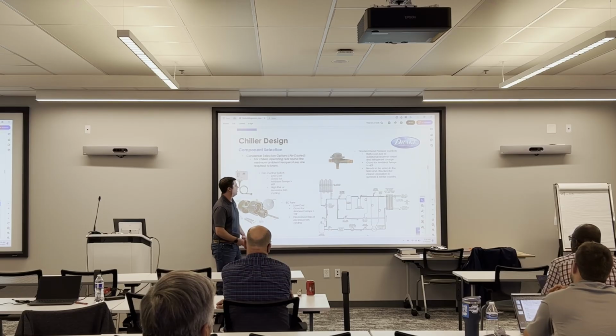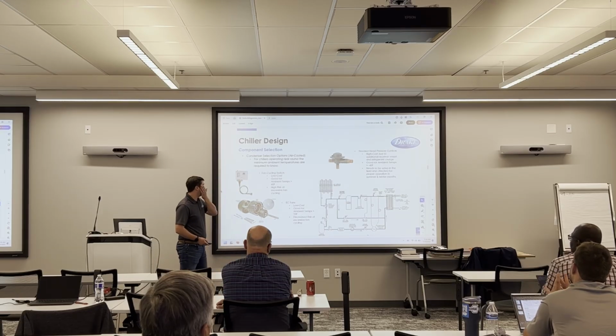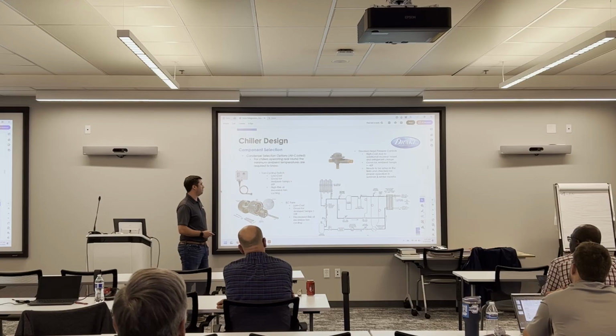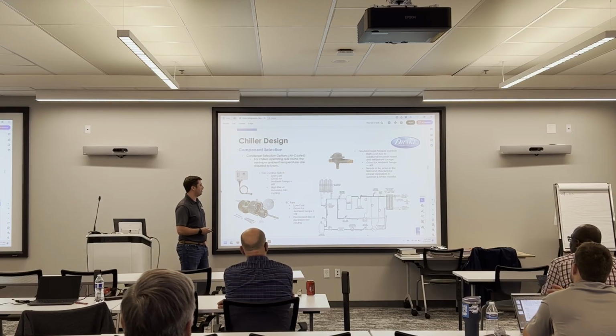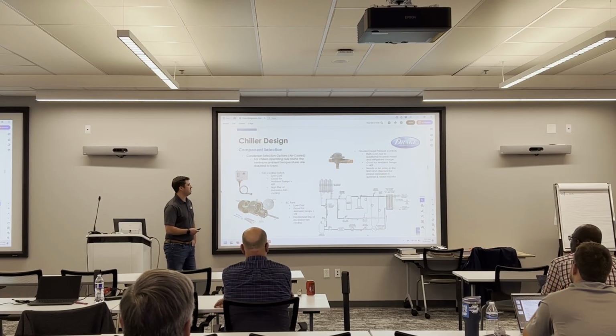So why do we have this stuff? If you don't have any sort of means of controlling your discharge pressure, your refrigerant's not going to flow properly through the refrigeration circuit. If you can keep your head pressure up, we use medium pressure refrigerant, so ideally we like to keep our pressure at like 250, right about here, right under our transducer. If you can maintain 250 year round, the system's not going to give you any problems.